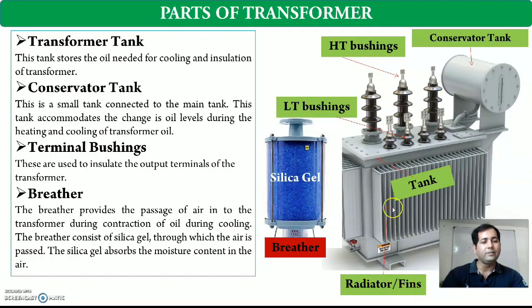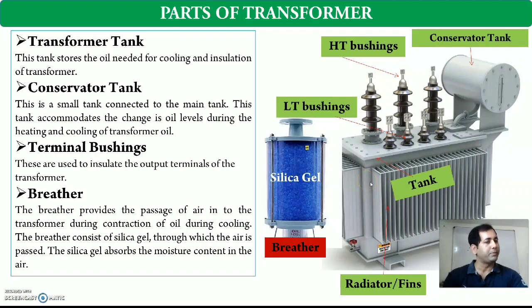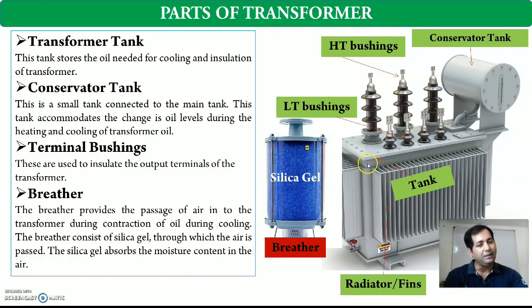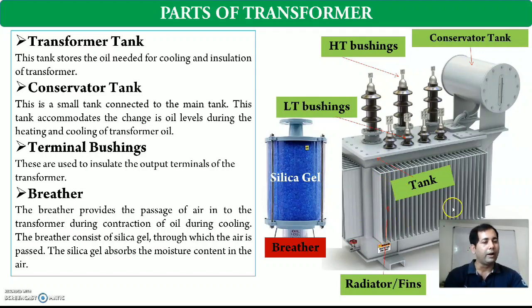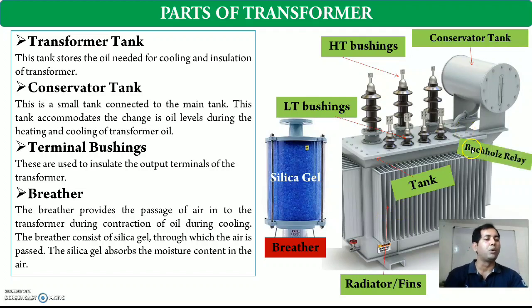The next point is radiator or fins, also an important part of transformer. When an oil-cooled transformer is loaded, heating occurs inside. The transformer oil absorbs heat, which reduces the oil density, causing hot oil to rise to the top while cold oil stays at the bottom. Through ventilating pipes, the hot oil flows into the radiator or fins, which contain thin pipes through which air is passed. Using natural and induced air draft, the oil is cooled. For cooling purposes we use radiators and fins, which are easily visible on three-phase power transformers.